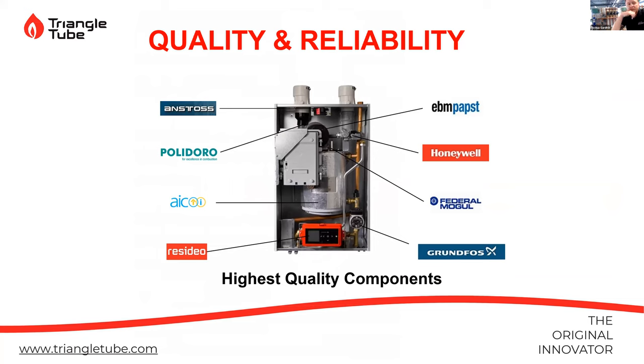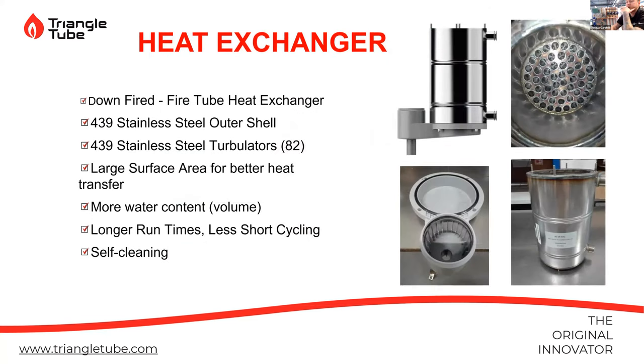We kept it pretty simple in this cabinet, which I really like on the boiler, but we made it very easy to service. So pretty much all these components we can remove without having to remove something else, which I think is the most important part. All these boilers, no matter what manufacturer, need service at the end of the day. They need to be serviced every year, so there are components in there that we need to change. Having those components be easy to remove and change is quite important when you're talking about service, as opposed to some of these units that cram everything in there as much as they can.